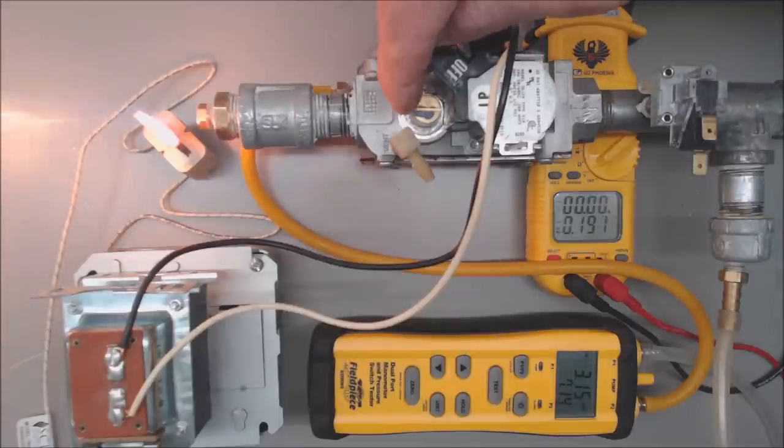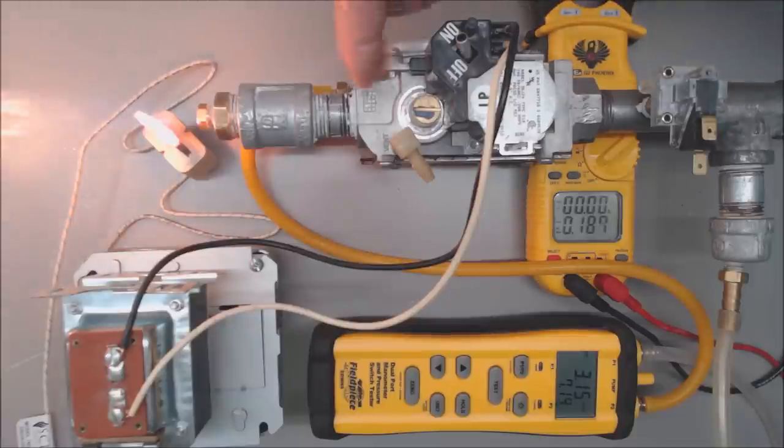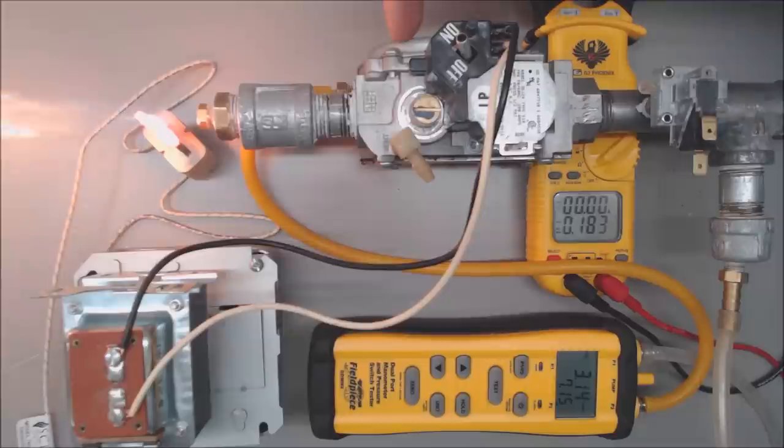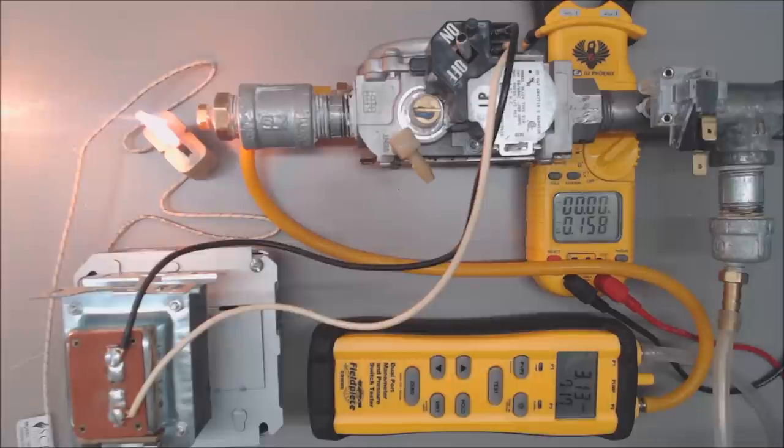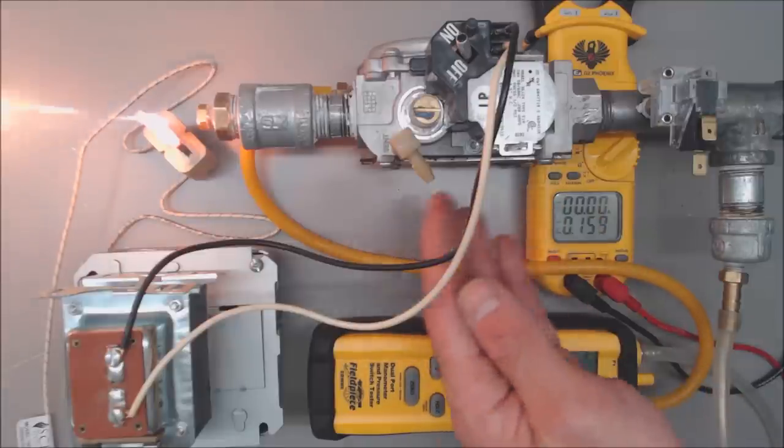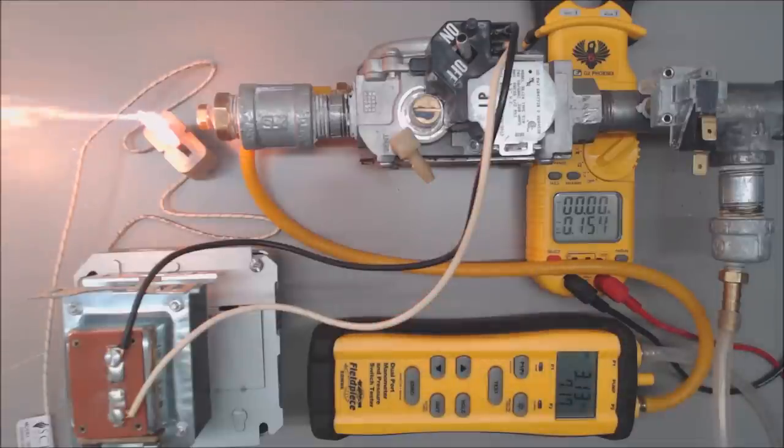As well, if you have this gas adjusted properly and it's actually pulsating, that could be another problem. Just make sure that you have steady voltage going to it and if it is pulsating and you have the correct spring in there, then that could actually be a faulty gas valve. You would also notice a problem when you're reading your combustion analysis as well when you have a pulsating flame or incorrect pressure coming through, something different than what it was actually designed for.